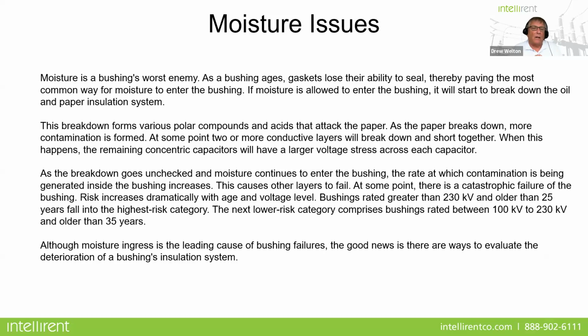So the one thing I really want to talk about today, and this is one of my favorite topics because I talk about it a lot, along with my colleague Brian, who's coming up last today, and that is moisture issues. Because moisture is a bushing's worst enemy. As a bushing ages, gaskets lose their ability to seal, thereby paving the most common way for moisture to get into the bushing. So if moisture is allowed to enter the bushing, it's going to start to break down the oil and paper insulation system, just like it would in a transformer. The breakdown forms various polar compounds and acids that actually eat away and attack the paper. And as that paper breaks down, more contamination is formed.